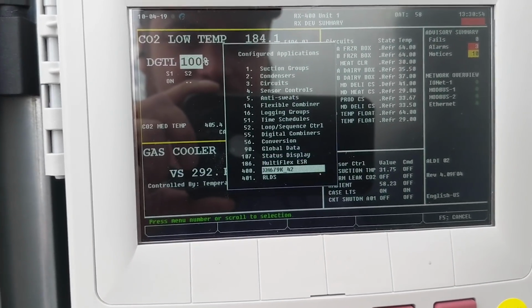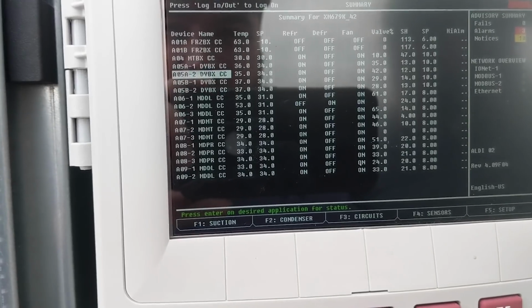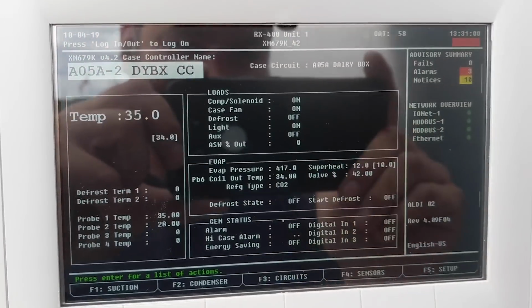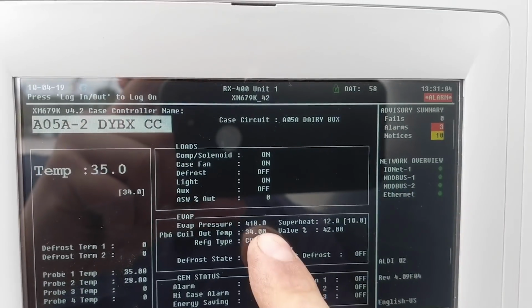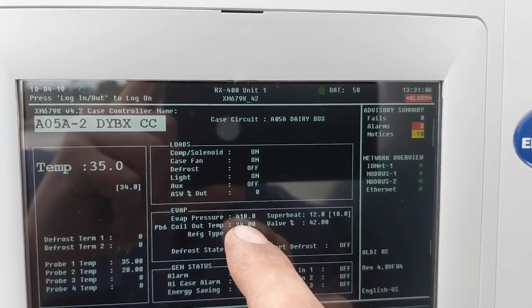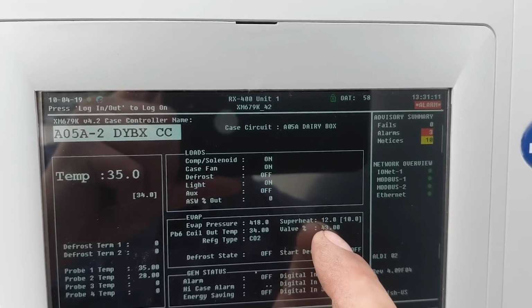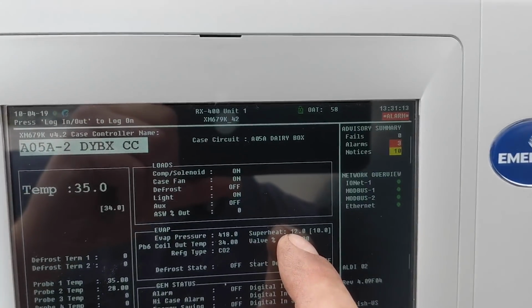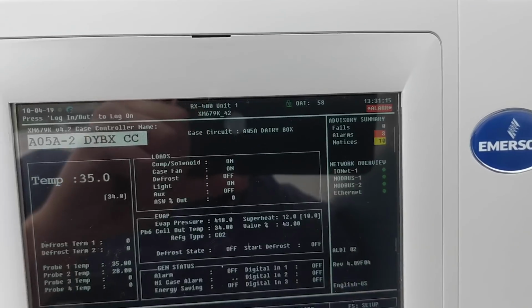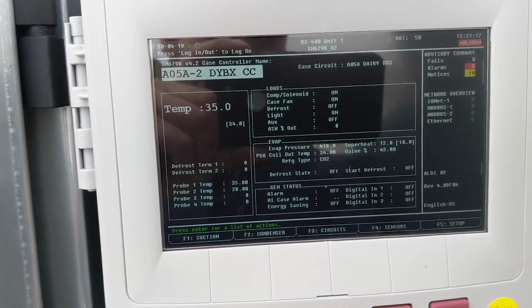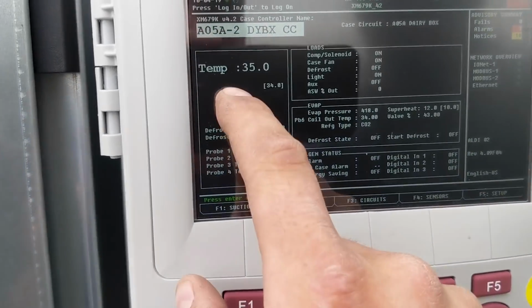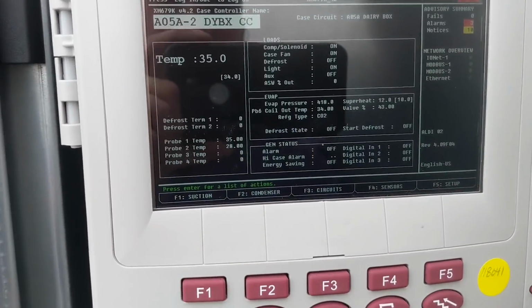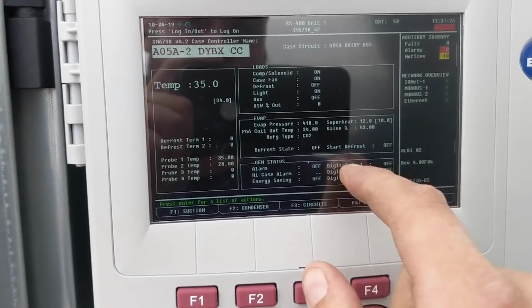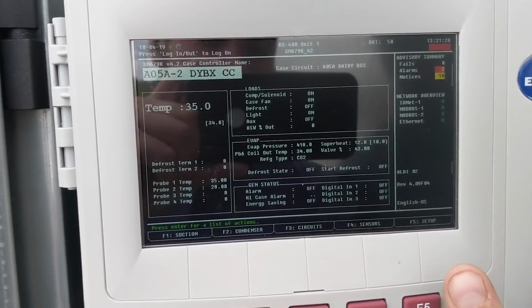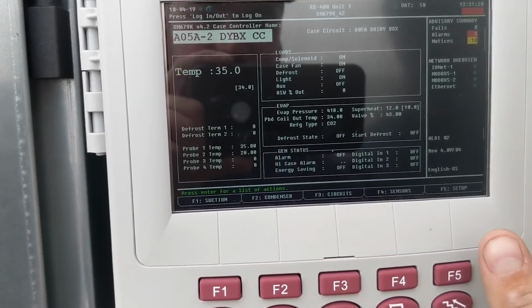So we're using Dixell XM679s. These valves are pulsing up and down. We have our evaporator pressure, coil outlet temperature, your valve percentage that it's pulsing, 42%, your superheat's 12 degrees, its set point is 10. So these are going to try to maintain temp and superheat. 35 degree box temp, it's trying to maintain 34, so it's a degree off set point, so that's why it's opening. These are going to maintain temperature and superheat second.